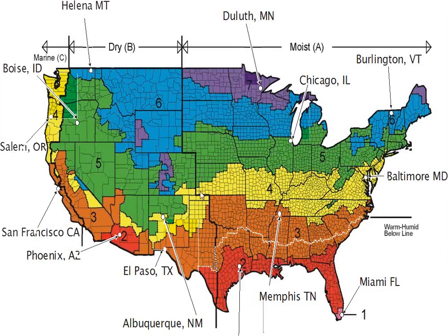The country has different weather zones that we're divided into. This is not just for this standard, but for many other ASHRAE standards. So if you are in Chicago, for example, where I am near right now, I am in climate zone 5, this green climate zone, and I am to the right of the magical moist humidification line here. So if you're on the right side of that line, you're in the A zone. So I'm climate zone 5A in Chicago.